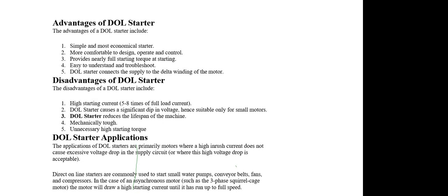Direct online starter reduces the lifespan of the machine. Of course, there is a continuous surge in the total system itself. So it is mechanically tough. As I said, if it is a huge motor, then the torque generated is very difficult to handle. If it's a very big centrifugal fan, then also it is very difficult to start it.